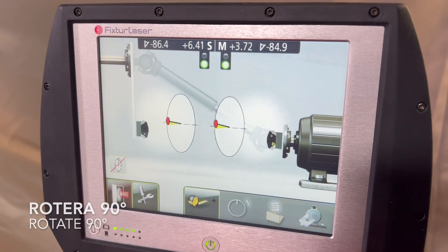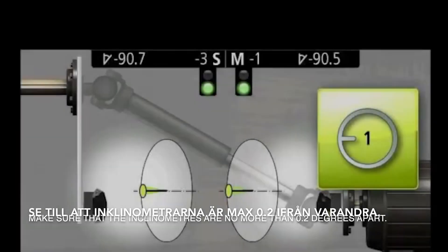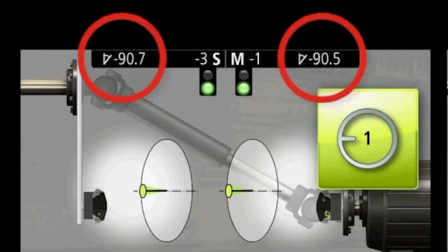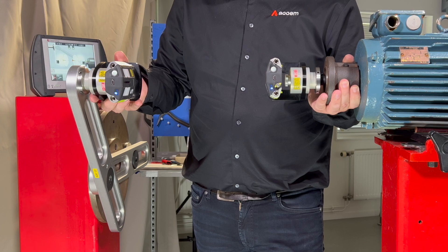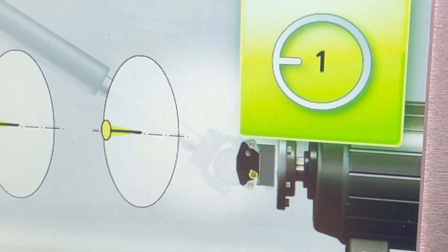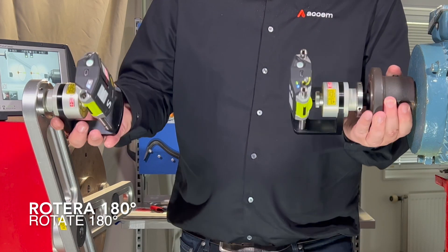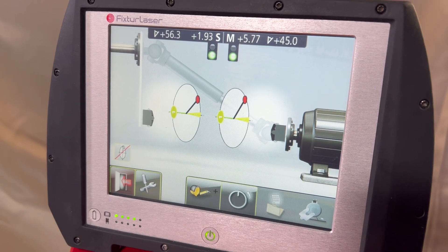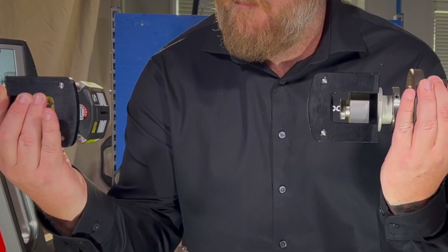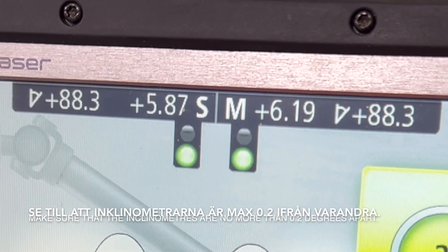Make sure to rotate the shaft, not the turret. Make sure that you are within 0.2 degrees from each TD unit. Rotate the TD units 180 degrees. Again, make sure to keep them within 0.2 degrees of each other.